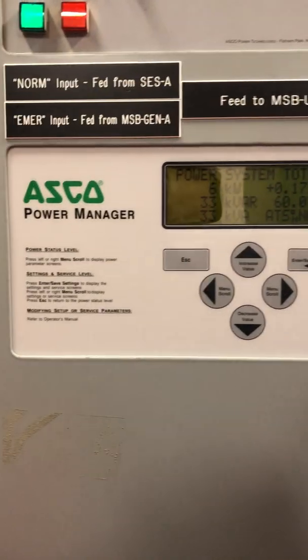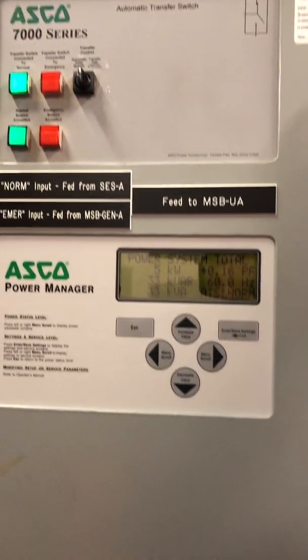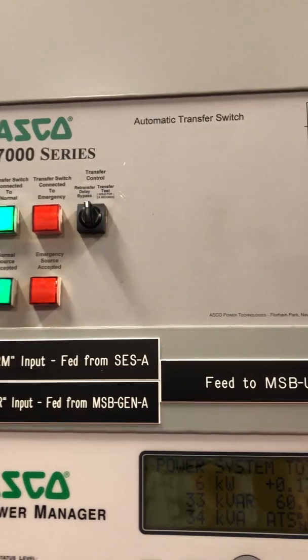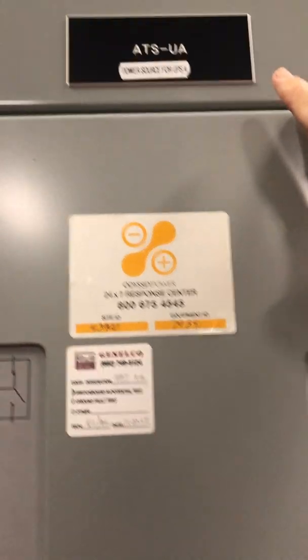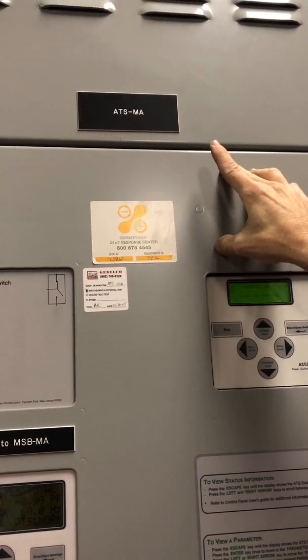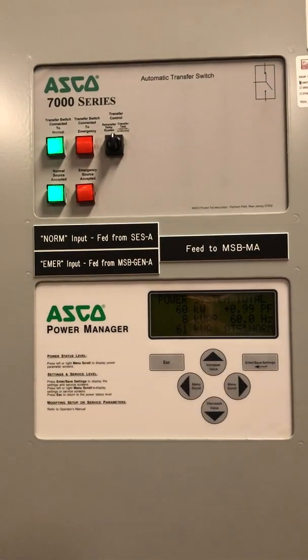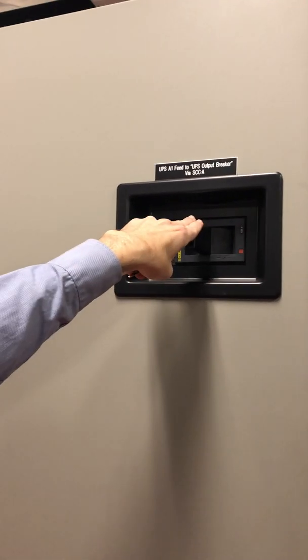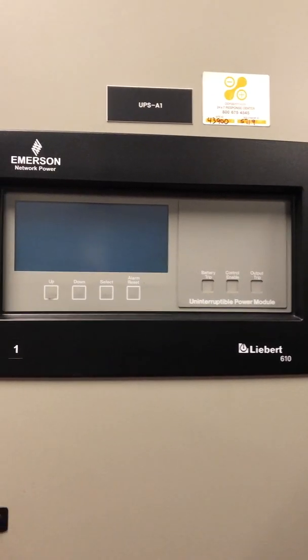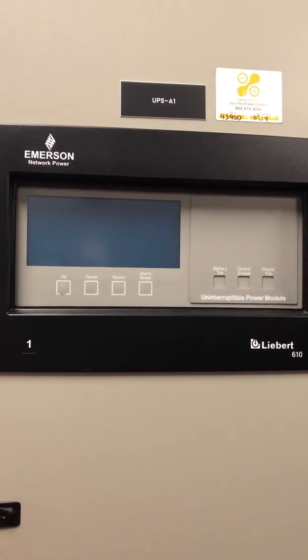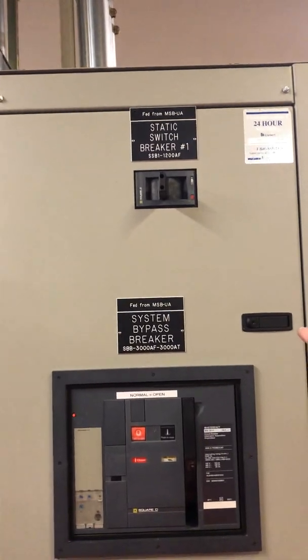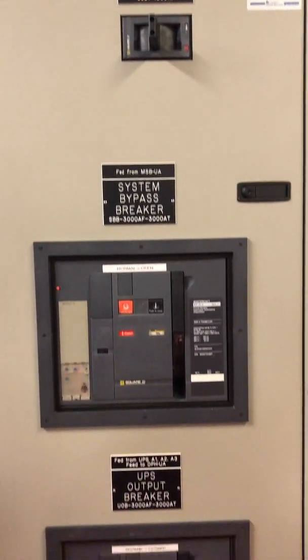To protect the site, we have multiple automatic transfer switches to split the risk. ATS UA is dedicated just to UPS A side power automatic transfer switch, and ATS MA handles the mechanical, lighting, and other supplemental wires. Right now, as there are no batteries attached to it, the UPS module is in standby, as you can see by the breaker being tripped into the not-off, not-on position, which is why it's in the center. You'll find the connections mirrored on the static transfer switch, preventing power going to the UPS module.